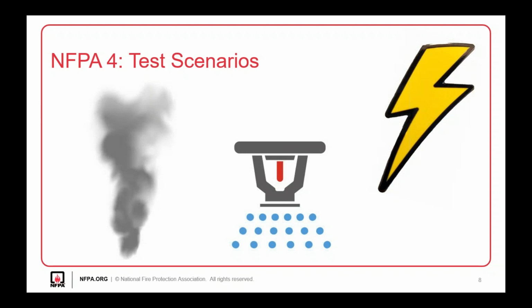The purpose of an integrated system test is to verify that all the required building functions occur. Each building and system is different, so you're really going to have to know your building inside and out to develop a test scenario or multiple test scenarios. Depending on the systems installed in your building and the circumstances they could be subject to, that will help determine what types of tests you'd like to conduct.